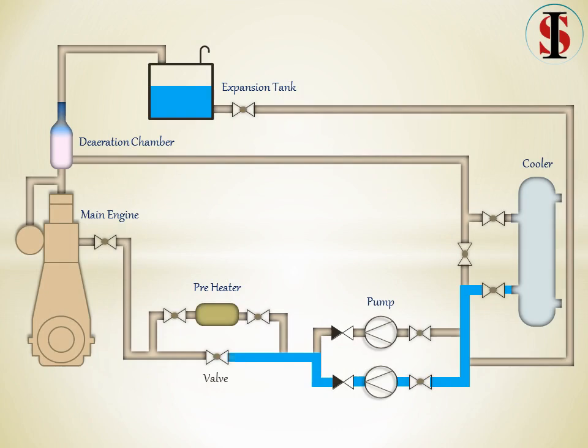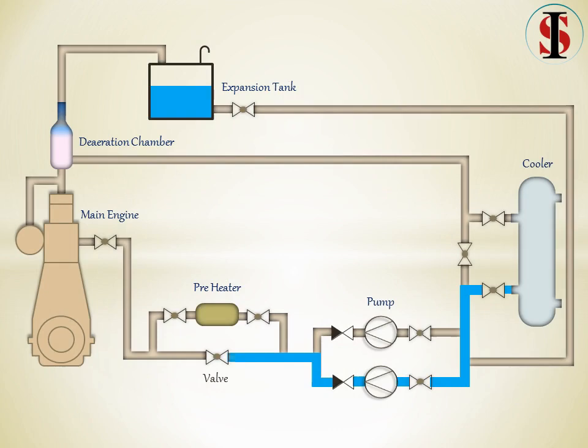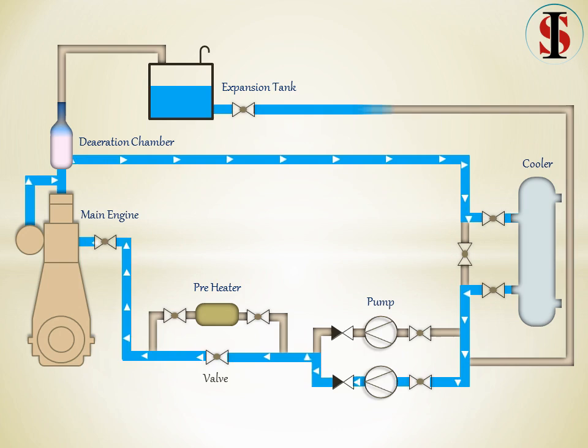The jacket cooling system is a closed circuit. Water passing from the engine returns through a cooler to the circulating pump and then back to the engine while the engine is running. A header or expansion tank is placed at sufficient height to allow venting and water makeup in the system.